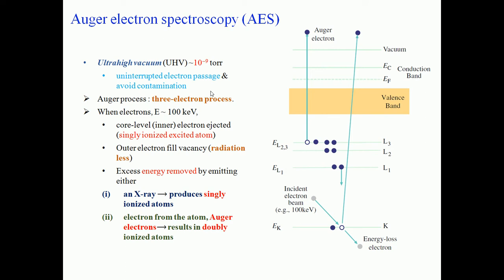For creating Auger electrons, you need ultra-high vacuum of the order of 10⁻⁹ Torr. This vacuum is necessary for uninterrupted electron passage and to avoid contamination. The Auger electron energy lies between about 100 eV to 800 eV, so you do not want to scatter these electrons — you need the actual signal. Therefore, ultra-high vacuum is required.